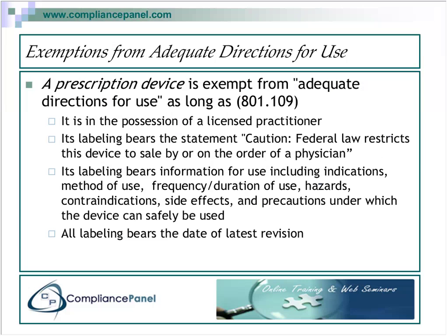There are exemptions from adequate directions for use, and a prescription device is exempt from adequate directions for use, which means that if you sell a device to a physician, you don't have to meet the requirements for adequate directions for use. To summarize this slide, you have to have the second bullet point, caution, federal law restricts this device to sale by, etc., etc. That must be on your labeling. It shows the FDA and the end user that your device is a prescription device and is exempt from adequate directions for use.